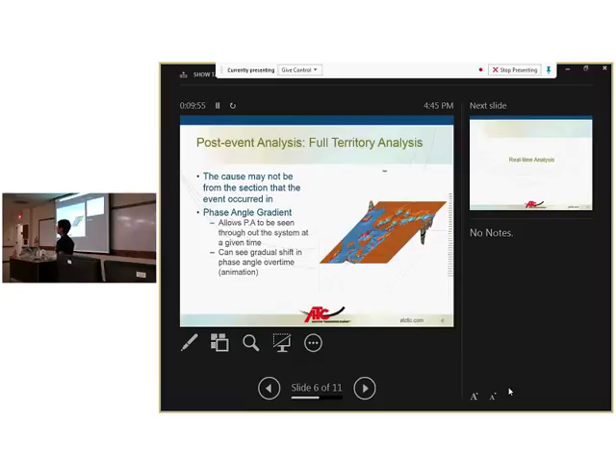It's the way PMU data works: it's all synchronized to a GPS time clock, so we're pretty certain, up to one microsecond, that they're all at the same time frame. Especially with the power grid being 60 hertz, it could move around a lot if it's not really accurate. So if it's only accurate to 1 millisecond, it might show a much different map of the phase angle, since it shifts around so much.